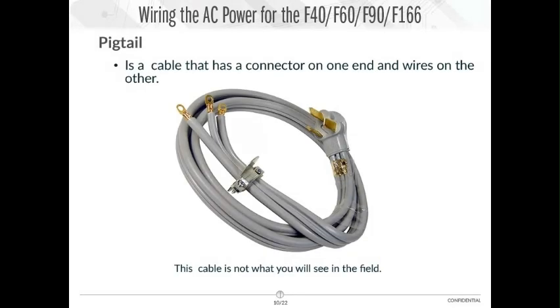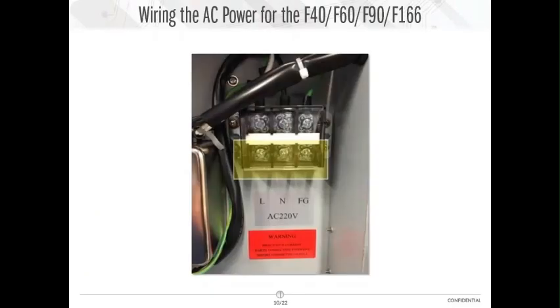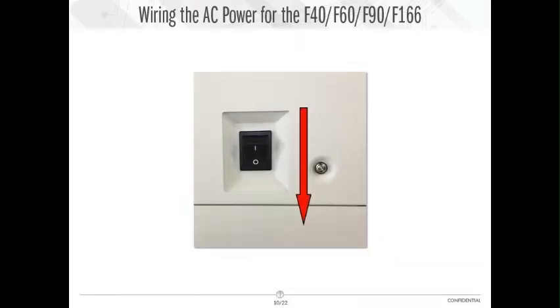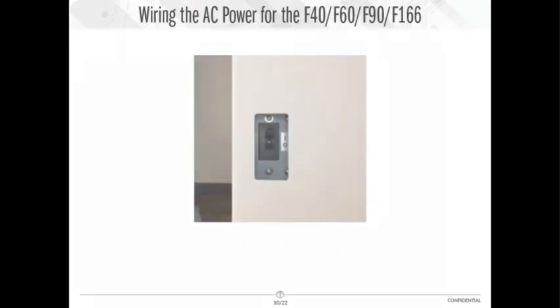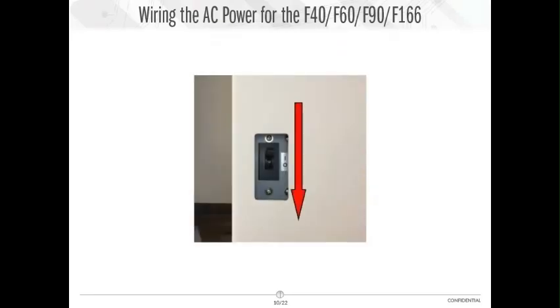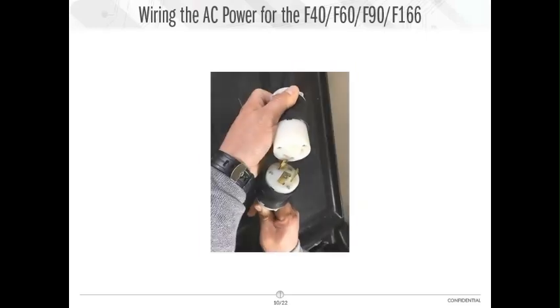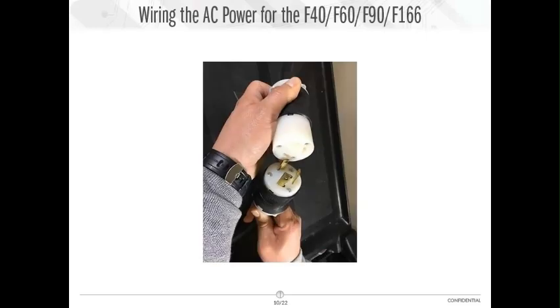A pigtail is an electrical cable that has a connector on one side of the cable and has 3 wires on the other side. We are going to connect the 3 wires to the printer. Before installing the pigtail to the printer, make sure the power switch is off. Next, make sure the circuit breaker is set to the off position. Also, make sure that the pigtail is not plugged into the socket or receptacle.